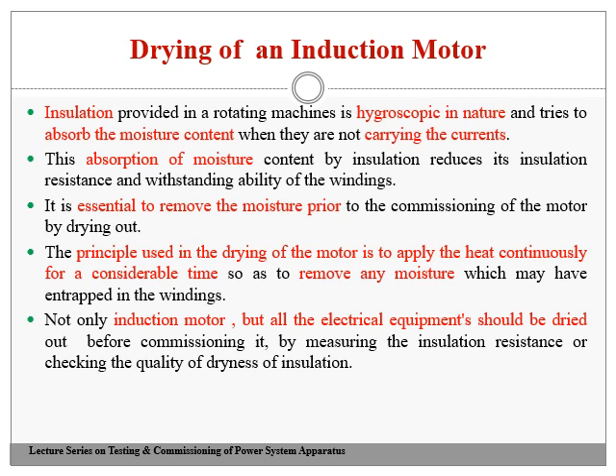This absorption of moisture content by insulation reduces the insulation resistance and the withstanding ability of the winding. Once the moisture gets absorbed by the insulation, it loses some of its electrical properties, hence at some time on application of voltage, it may become a conducting part. It is always essential to remove the moisture content so that I can keep the insulating properties as they were provided in the manufacturing or design condition. Therefore, the principle used in drying out a motor is to apply heat continuously for a considerable amount of time so as to remove any moisture content which may have been entrapped in the winding. Once the moisture gets absorbed, as I said already, insulating properties reduce. Hence, to bring back that insulating property to its original position, it is always essential to remove the moisture content. How to remove the moisture content?